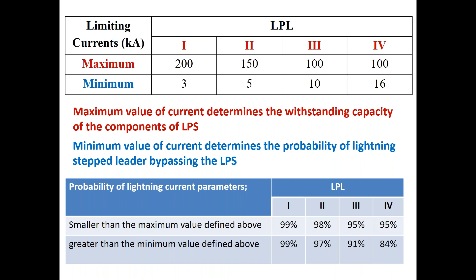So the table below shows the percentages of such success in the case of lightning protection systems. For example, if you go to the maximum lightning current case, if you go to level 4 protection, in 95% of the cases the current will be less than the value given for level 4 protection. So there is a chance of 5% of failure. If you go to the minimum case, level 4 protection, just as an example, there is a 16% probability of the step leader being missed or bypassing the lightning protection system.